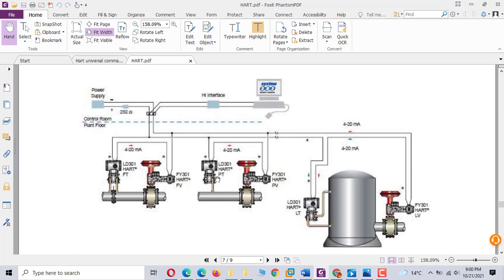Here is the pressure transmitter and this is the pressure valve. It has the PID. The pressure signal goes to the PID, then is sent to the pressure valve, the positioner. Then it opens or closes. This is the level transmitter. It also has PID capability, then goes to the level valve, the positioner. Then the signal goes to the PC, so the operator can control.